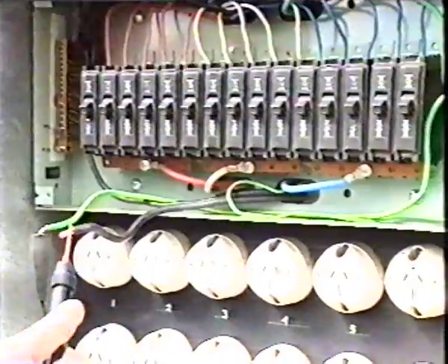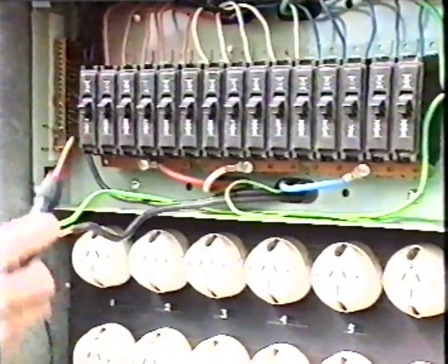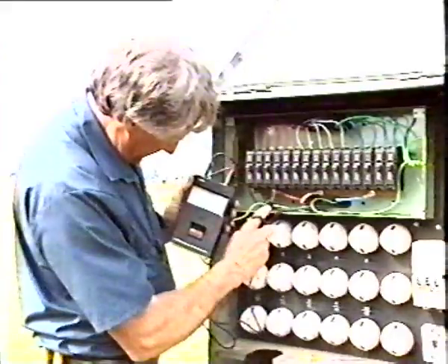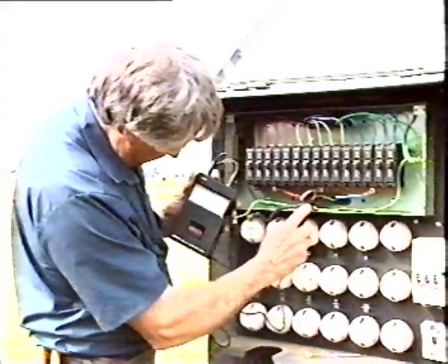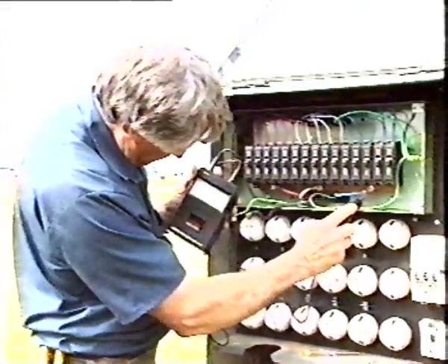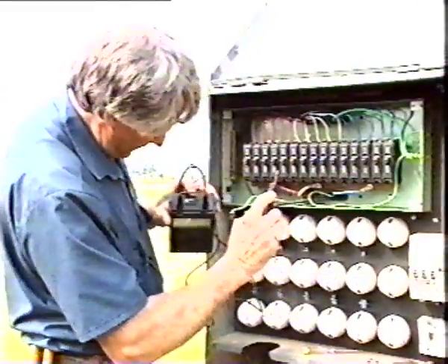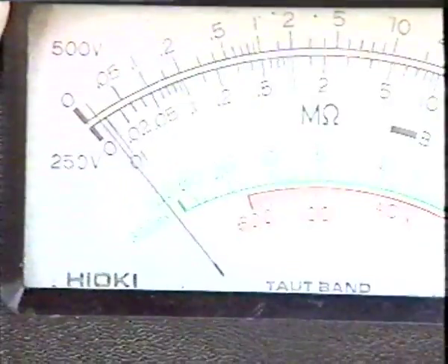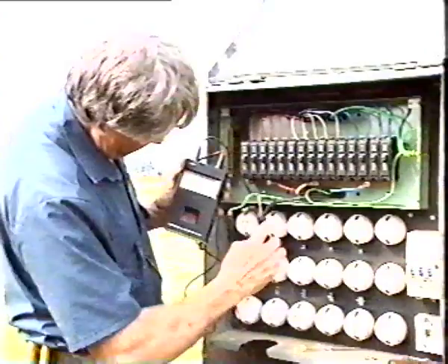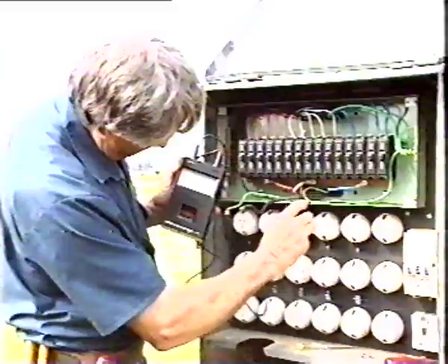Connect one ohm meter lead to the main earthing conductor at the distribution board and the other ohm meter lead in turn to the neutral and active conductors. Neutral to earth should indicate a short circuit and active to earth should indicate an open circuit. However, as the neutral to earth resistance depends upon the earth resistance back to the supply switchboard, it may be necessary to select a higher resistance range or even use the 500 volt range of the insulation resistance tester to verify the connection between the neutral conductor and the earthing system.